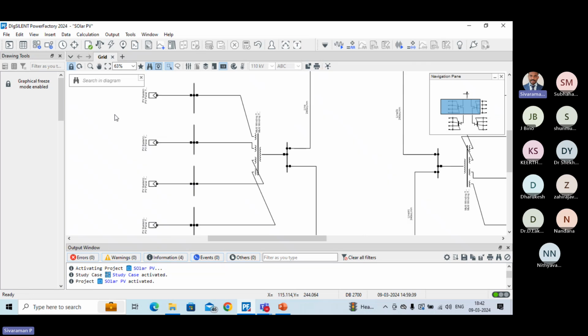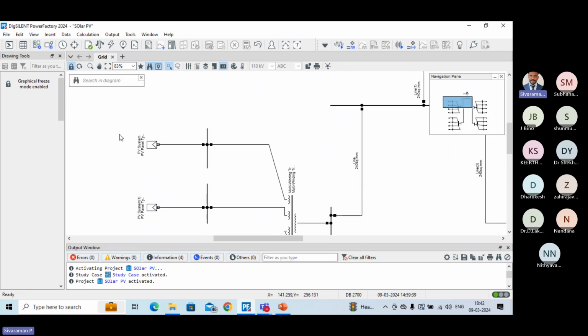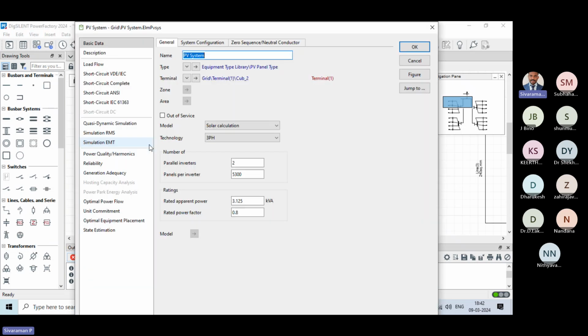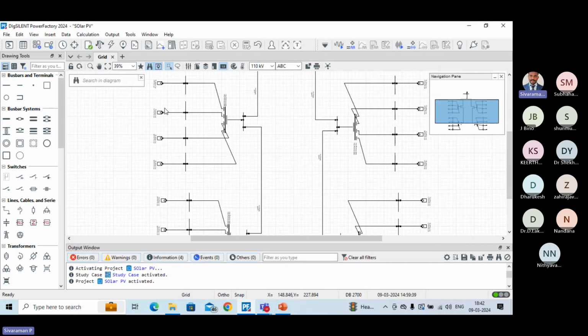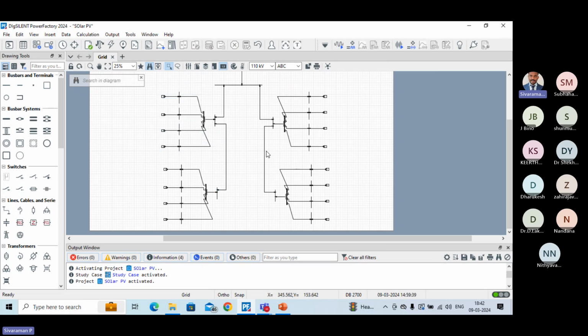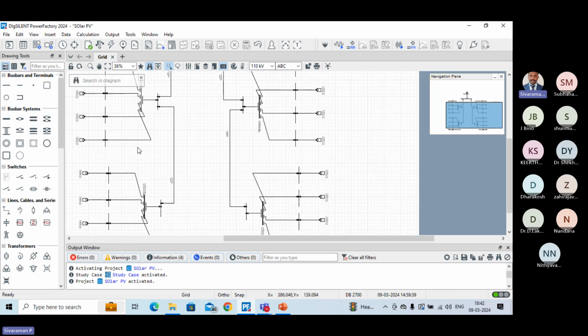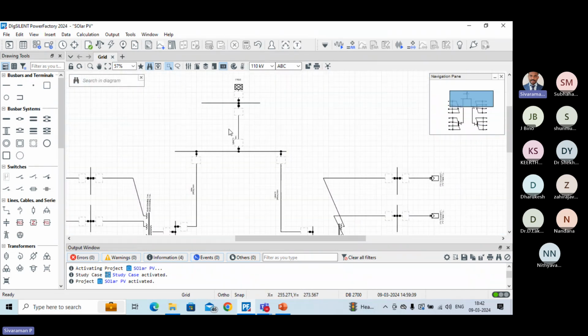It will be connected to the PV panel. This is the PV panel in DIgSILENT PowerFactory, equally rated at 3.125 MVA. We have rated this inverter at 3.125 MVA. Similarly, up to this point will be one inverter block, this will be the second inverter block, this the third inverter block, and this the fourth inverter block. So now the plant capacity is equivalent to 50 megawatt.